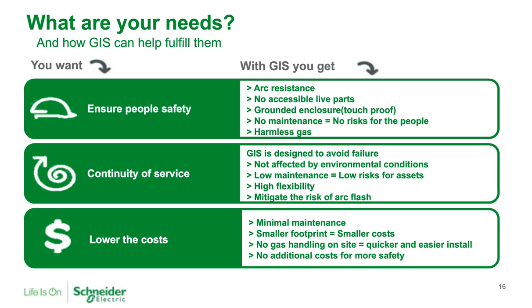Next point is continuity of service. Again, GIS is designed to avoid failure. Because your medium voltage circuit is insulated in gas, you're not exposed to dust, you're not exposed to humidity, you're not exposed to a lot of the external influences on the circuit which make you have to do maintenance and also cause problems down the line with switchgear.